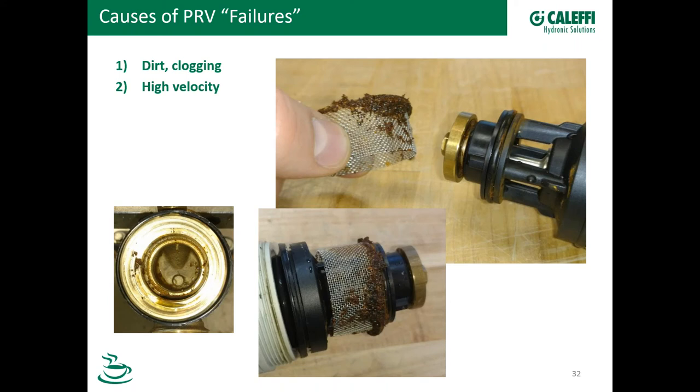High velocity is another problem. If you have too much velocity or too much pressure reduction in a valve, you have the possibility of noise, erosion, and vibration. Also, as the screen plugs up, you'll get less flow through the valve — you might think your valve is undersized and causing a lot of pressure drop, but in fact it could be the clogged screen. Just like a Y strainer at 75% plugged, you've got quite a bit of pressure drop. So isolation valves on both sides are wise; this is a maintenance item where you need to be able to get in there and clean the screen from time to time.